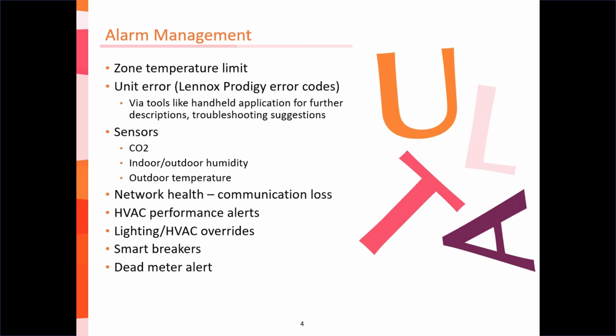You can also see overrides, both remotely and at the store level. Any breaker issues, we've got Square D lighting at a lot of stores. We can see if there's breakers that are being overridden, and that's another big way we can drive energy savings.